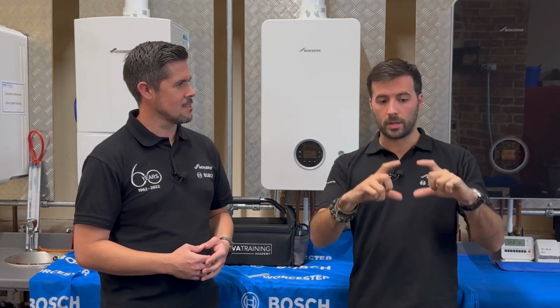It's worth noting that recently, because of the types of boilers and equipment we have, we're starting to look more at RCDs. So what you might come across is these RCD fuse spurs. Normal fuse spur, 3 amp fuse in there, but it's got 2 switches, one for test and one for activate, and the RCD is built into it. When it trips, when it fails, it cuts the live and the neutral. That's why we do that.